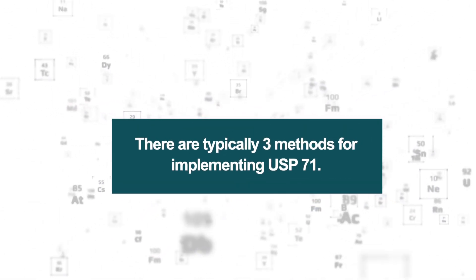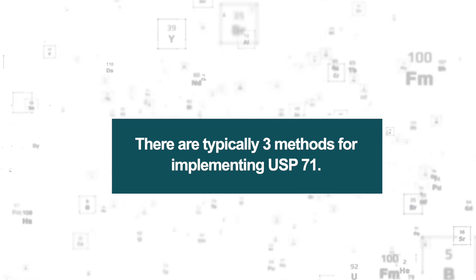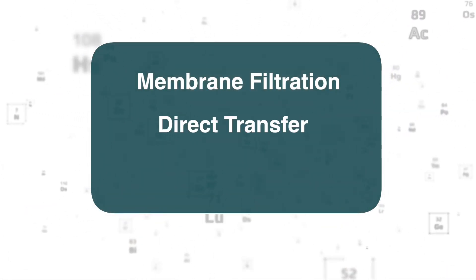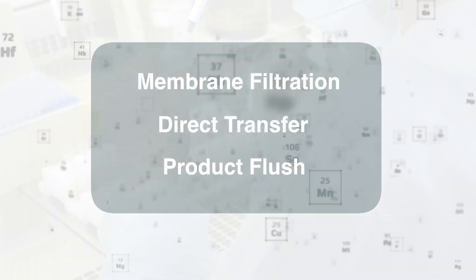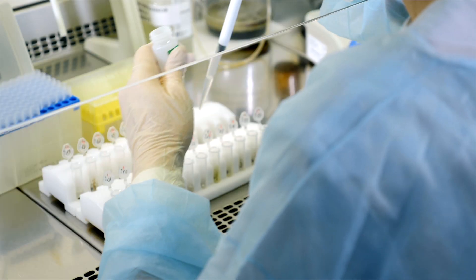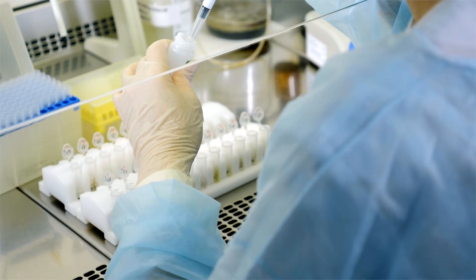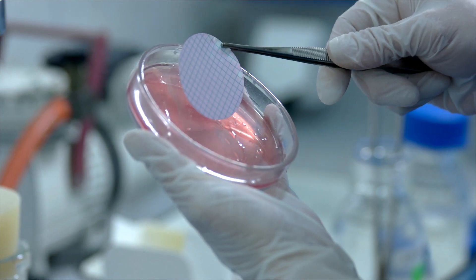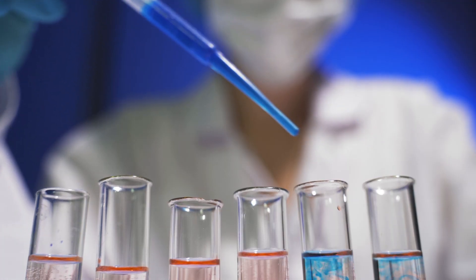There are typically three methods for implementing USP-71. These methods include membrane filtration, direct transfer, and product flush. Oftentimes, laboratories will perform method suitability for each specific product formulation to ensure that the appropriate method is chosen for testing.